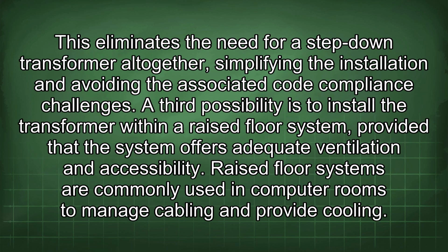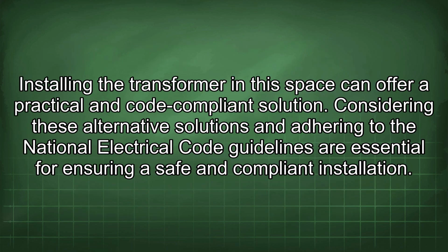This eliminates the need for a step-down transformer altogether, simplifying the installation and avoiding the associated code compliance challenges. A third possibility is to install the transformer within a raised floor system, provided that the system offers adequate ventilation and accessibility. Raised floor systems are commonly used in computer rooms to manage cabling and provide cooling. Installing the transformer in this space can offer a practical and code-compliant solution.